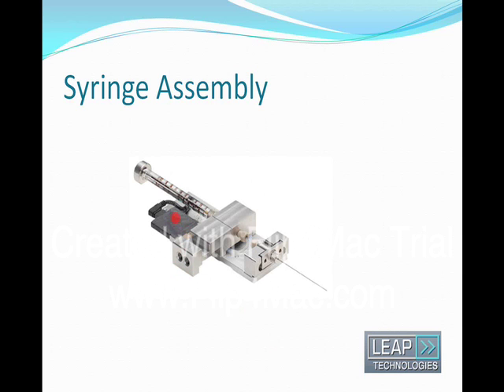This is the solvent selection valve. It's a solenoid valve which opens one or other of these two ports or closes them both. It's actuated using electronics in the injection head so there's no external electrical wiring required.